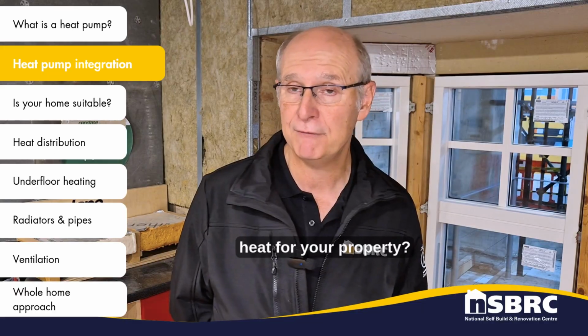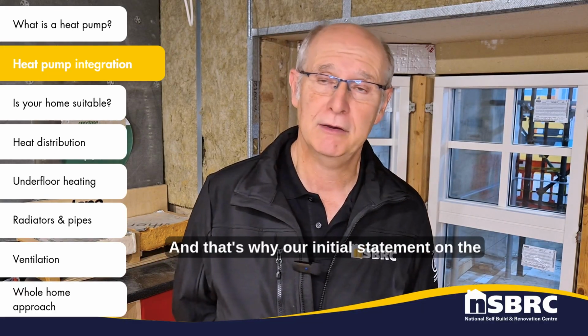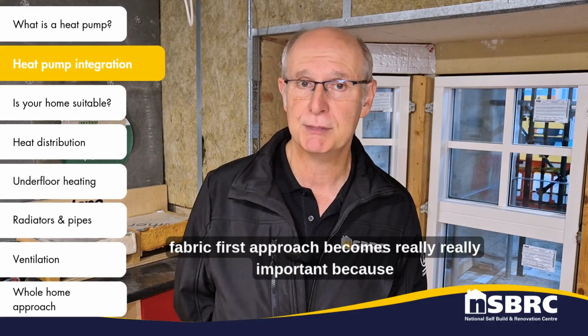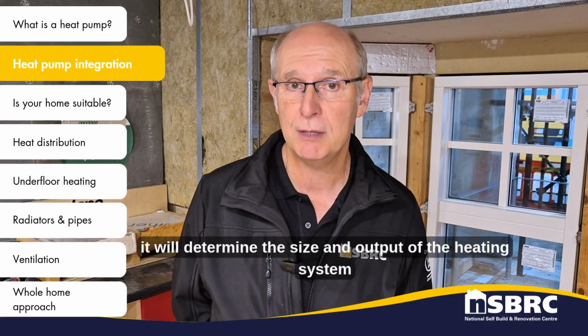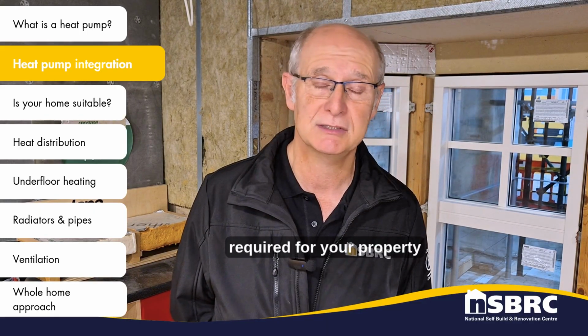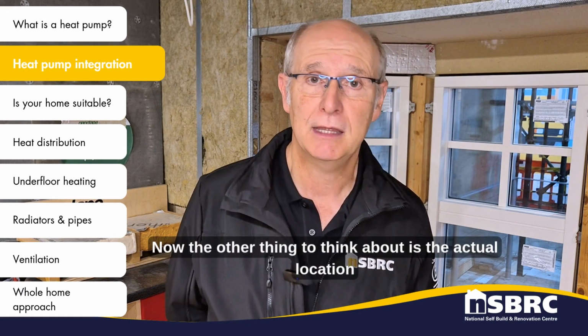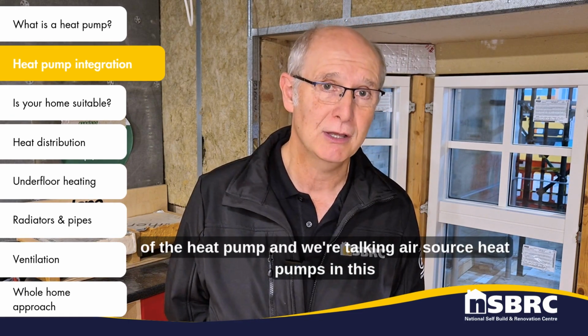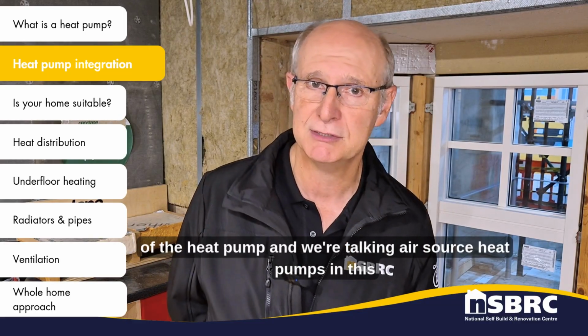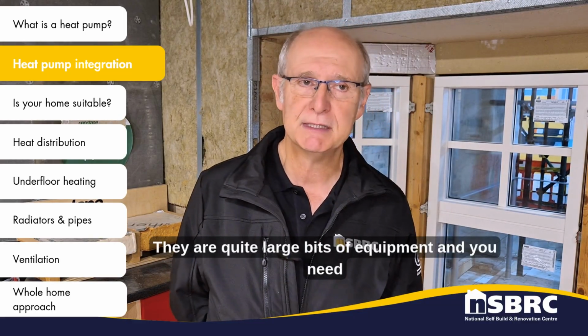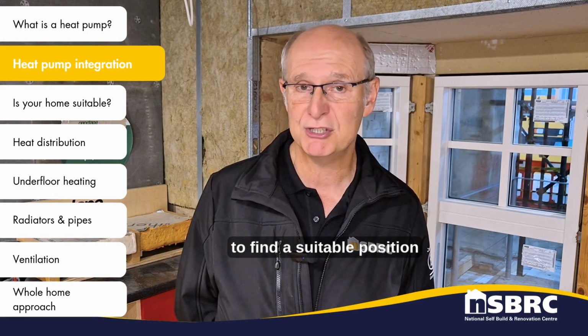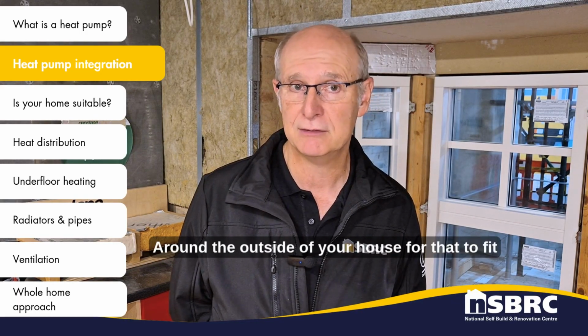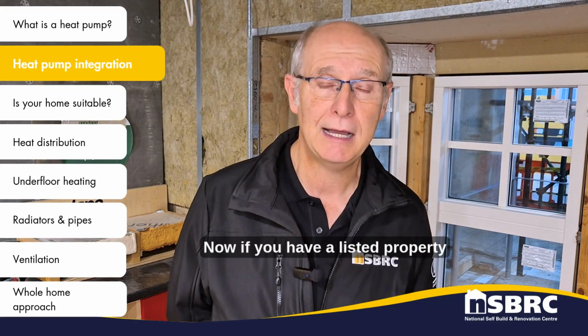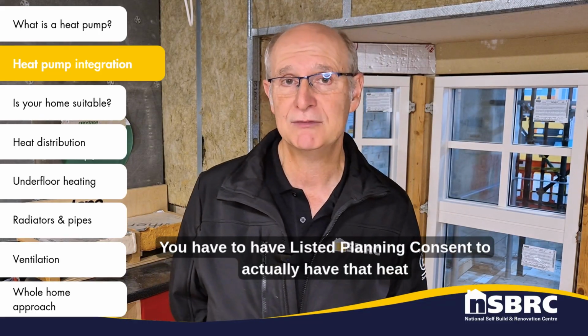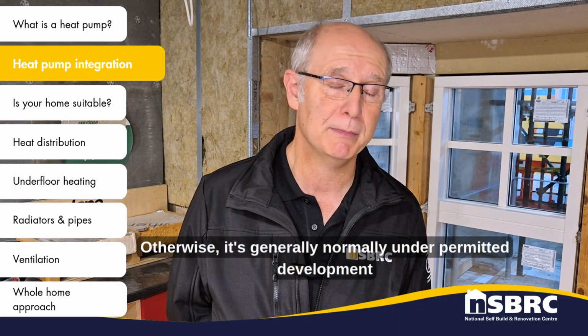Can it provide enough heat for your property? And that's why our initial statement on the fabric first approach becomes really, really important, because it will determine the size and output of the heating system required for your property. Now, the other thing to think about is the actual location of the heat pump. And we're talking air source heat pumps in this situation. They are quite large bits of equipment, and you need to find a suitable position around the outside of your house for that to fit. Now, if you have a listed property, you have to have listed planning consent to actually have that heat pump fitted. Otherwise, it's normally under permitted development.